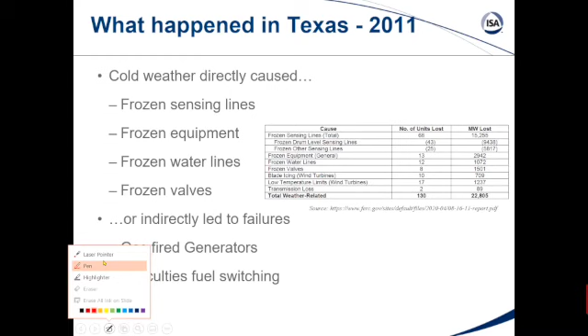This data comes straight out of the FERC report, which we'll give you at the end with all the links. The FERC report highlighted frozen sensing lines - specifically, they lost 15,000 megawatts in 2011 due to frozen sensing lines, like drum level sensing lines, meaning boiler drum level, plus other sensing lines. So about 15,000 megawatts from frozen sensing lines alone - think of a traditional differential pressure transmitter with impulse tubing lines. Other causes included frozen equipment and frozen water lines, etc.